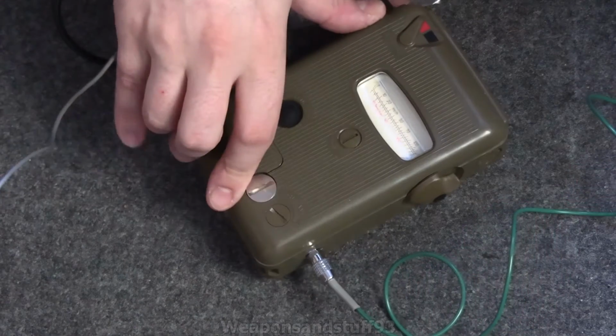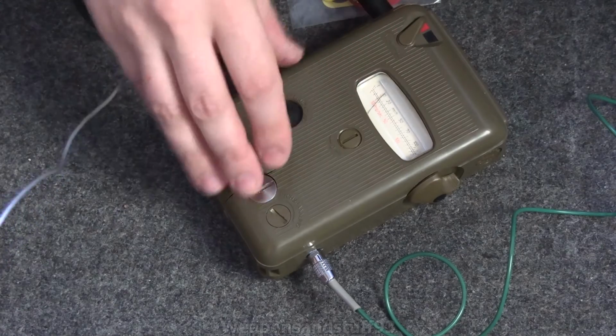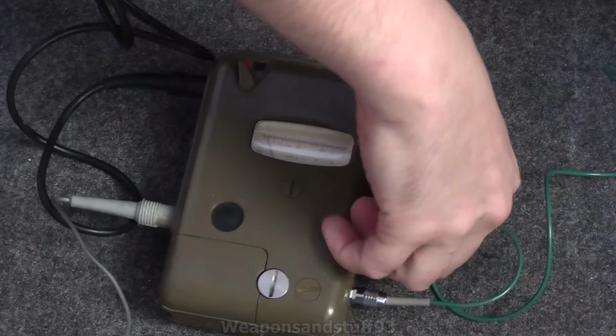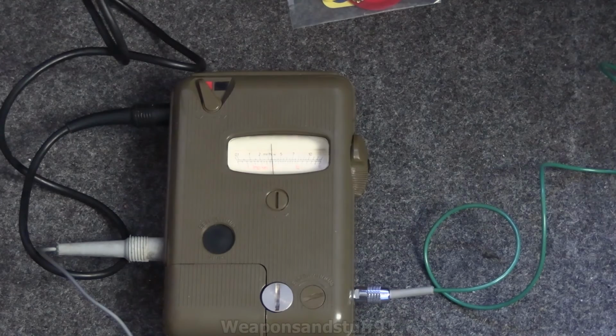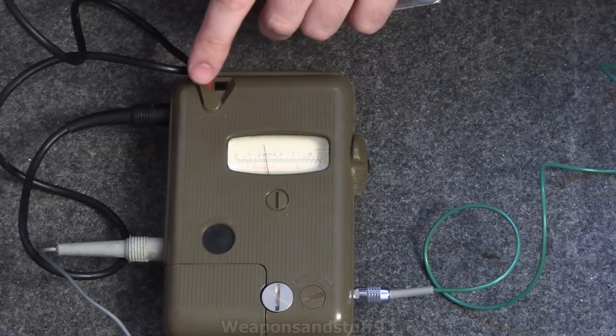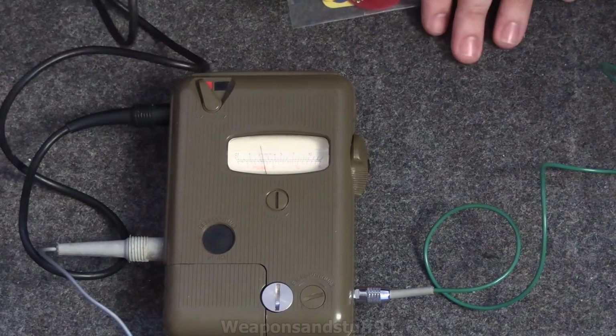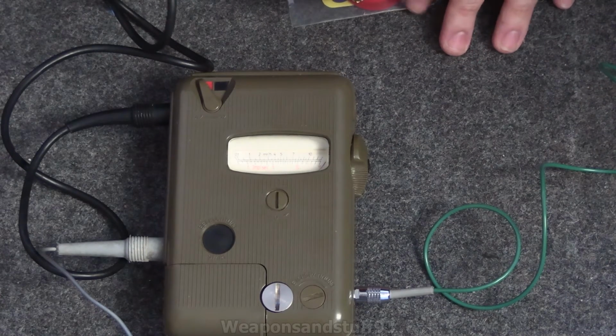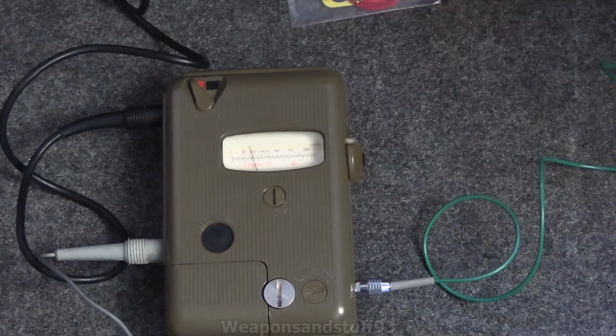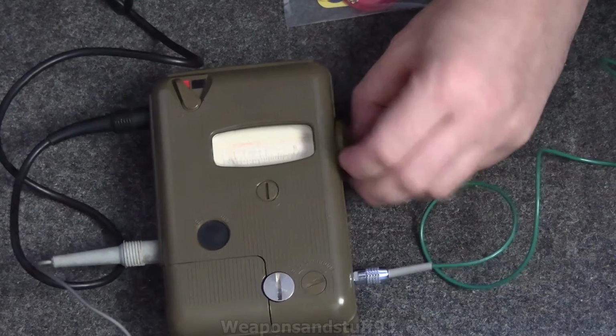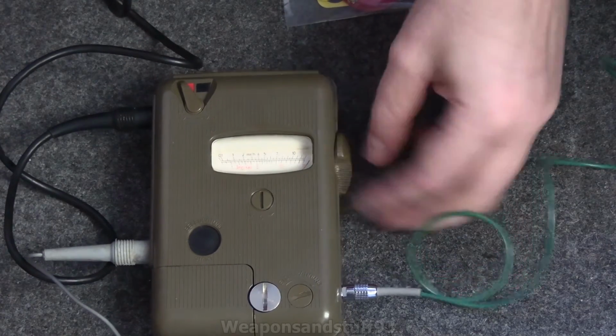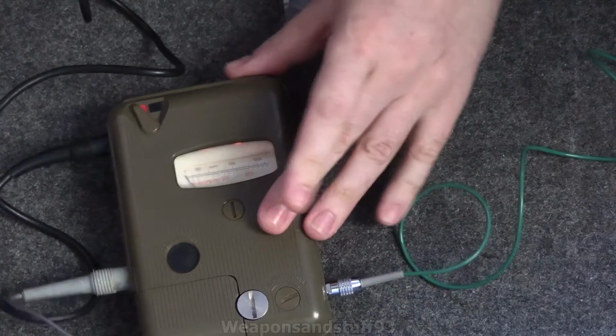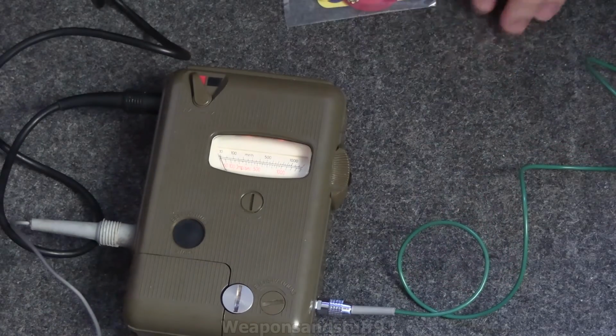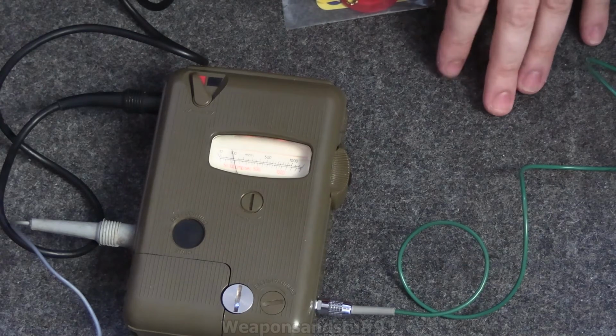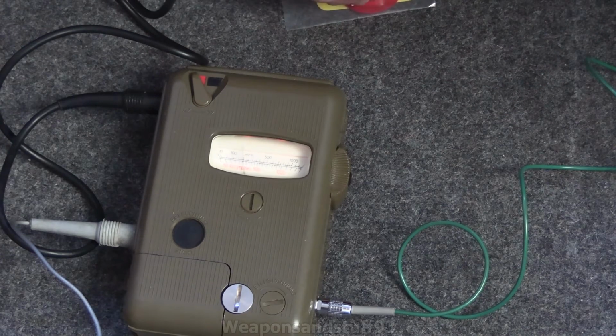That's gone off scale. But again, this is using the probe that's designed more for CPM or whatever. Because you're meant to be, if you're using this one, referring to the bottom bit anyway, but... And then let's go to our, or have I gone backwards there? Oh no, I went backwards that way. Right. So now we're on the 1 to basically Roentgen scale. I think this probe does pick up alpha radiation because of how sensitive it is.